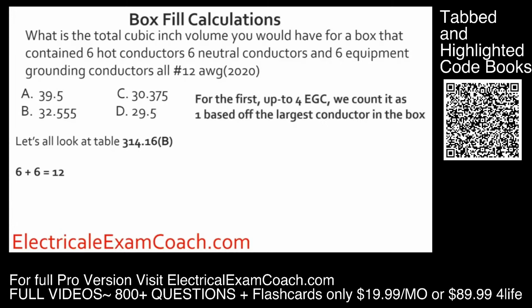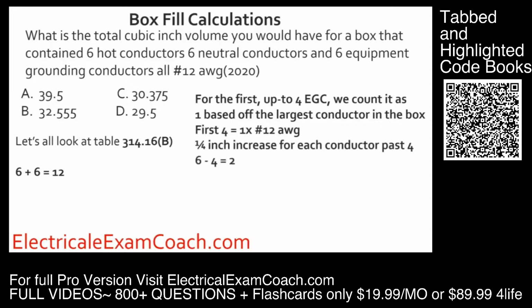We're going to, for the first 4, it's going to count as 1. So we need to figure out how many we are past 4. We have 6 total, minus that 4. That means we are 2 past 4. For each one of those, it's going to be a 1/4 inch increase. Take 2 multiplied by 0.25, that equals 0.50. Then we have our 1 original. Then we have 0.50 add-on. So that gives us 1.50 grounds.